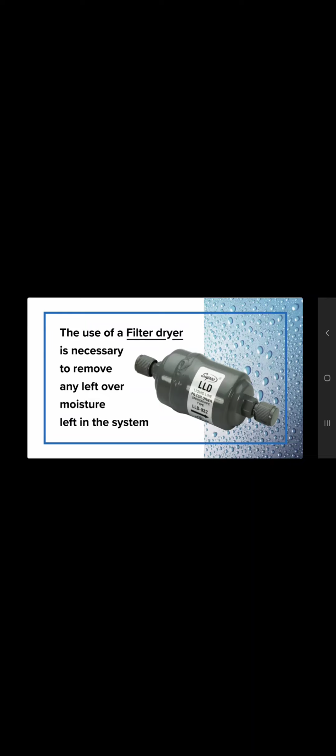So the 3 things I like to do anytime I open my system up to the environment: I'm doing a full pressure test, I'm making sure I replace that filter dryer, and I'm doing a full 500 micron vacuum. Very important things.